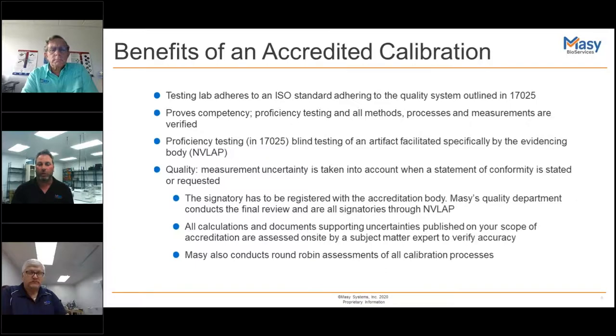Quality: measurement uncertainty is taken into account when a statement of conformity is stated or requested. This is a big one—a 2017 add-on. Previously, customers who may not have understood uncertainty could get a measurement reported with a pass-fail statement without factoring uncertainty into the equation. There wasn't a strict requirement; it was kind of loosey-goosey.